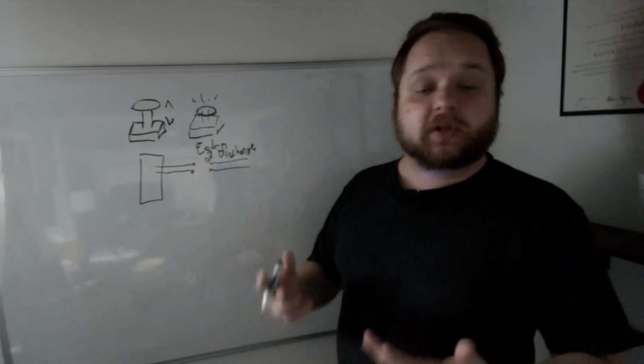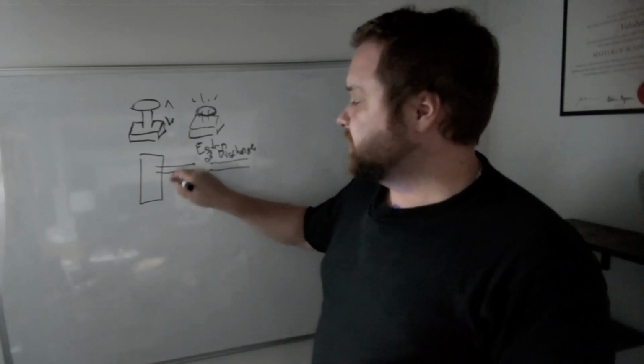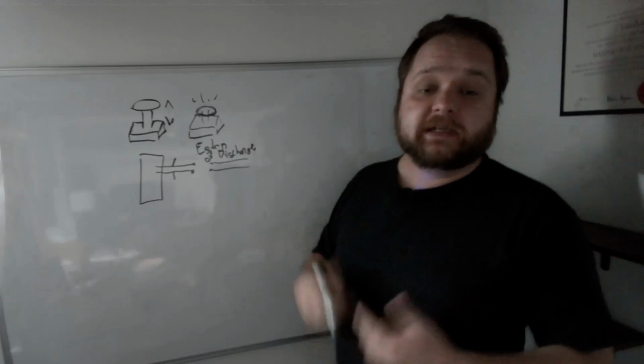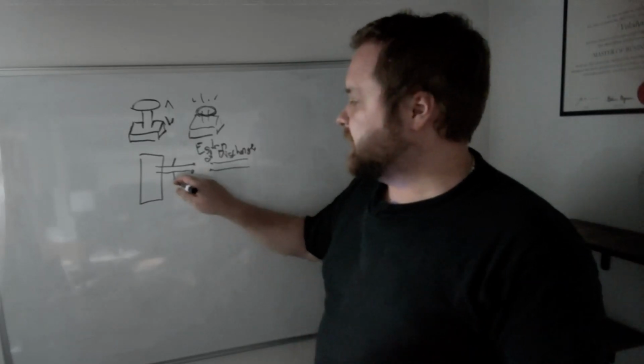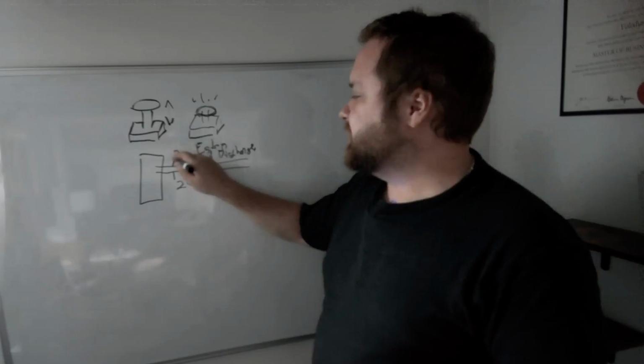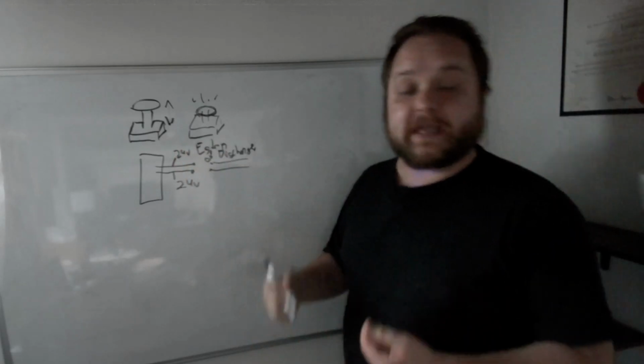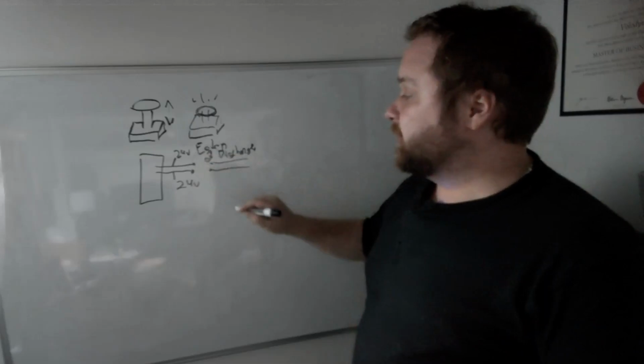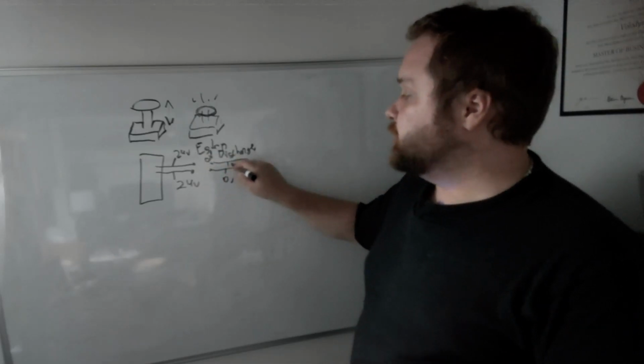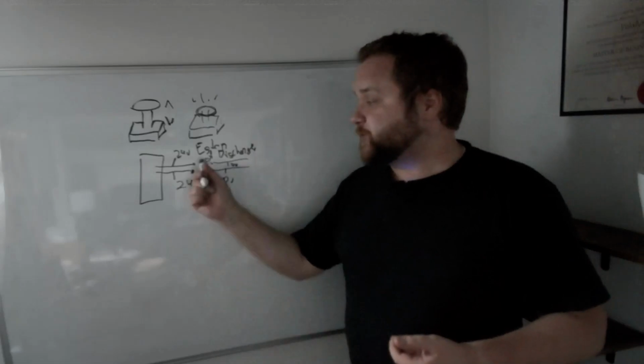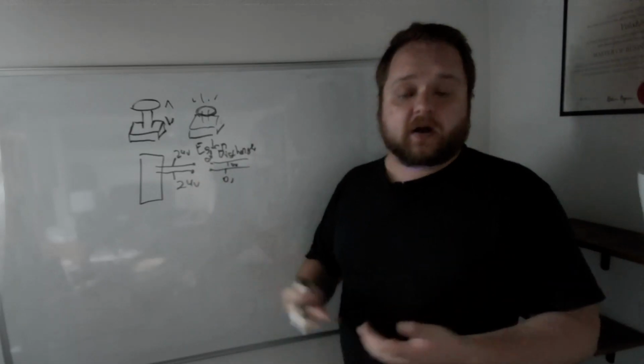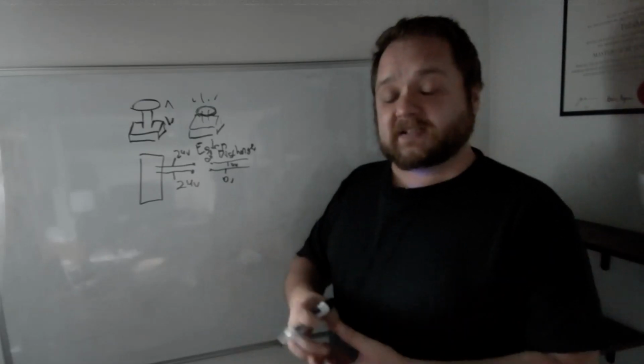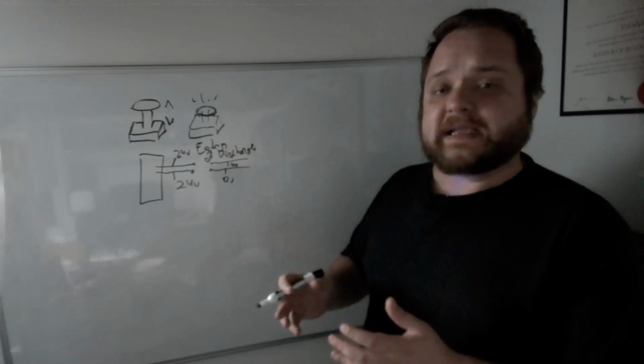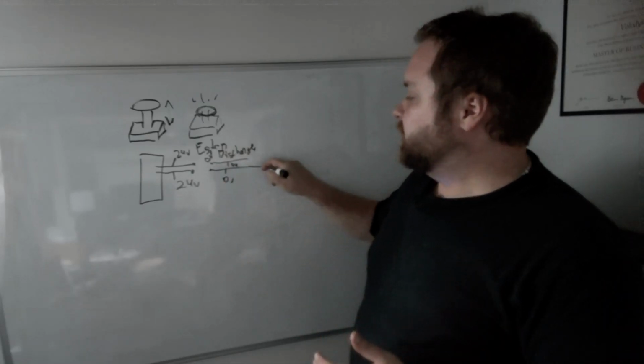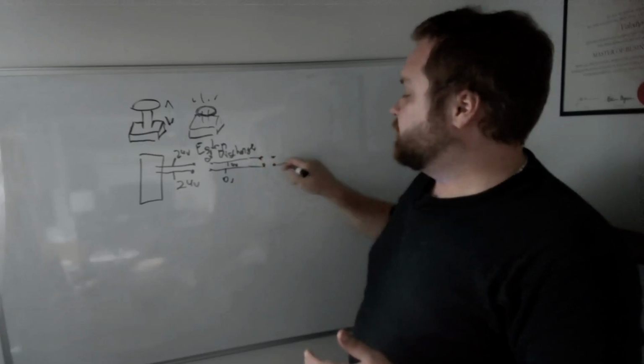Like I've mentioned a little bit earlier, what you need to be doing is measuring voltages. So your schematic and your device will tell you exactly or confirm that's the case, but a lot of times all you're doing is tracing the 24 volts around a loop. And like I've mentioned, if you're measuring 24 volts here and then you're measuring 0 volts here, you can immediately tell that your e-stop specifically here is not being made. And again, obviously in a normal e-stop that is functioning, that's going to be indicated by the light, and that is usually wired on a different circuit. But anyways, the point is that you should be measuring your loop around the various devices on your chain.